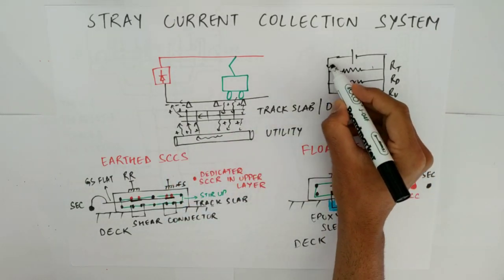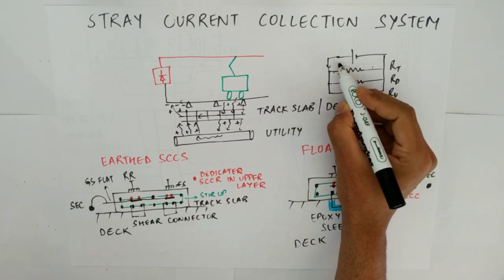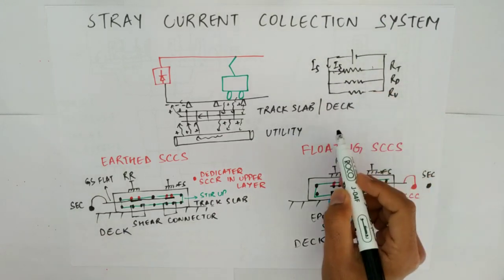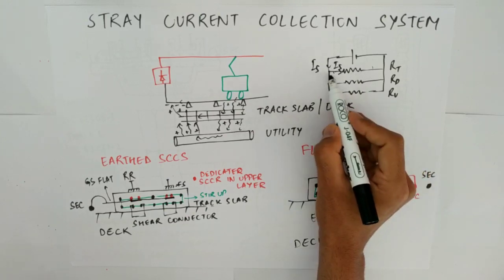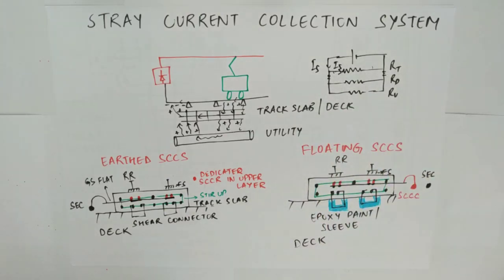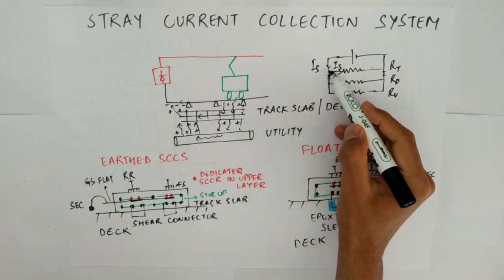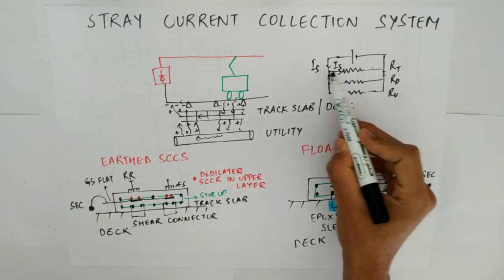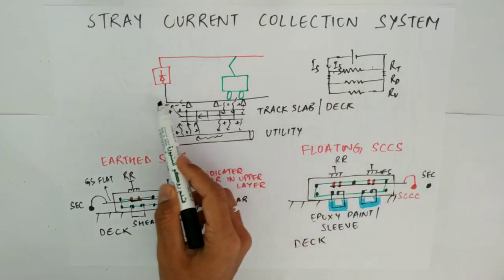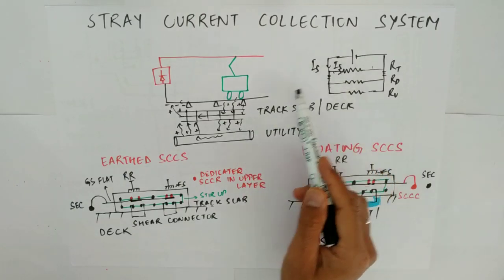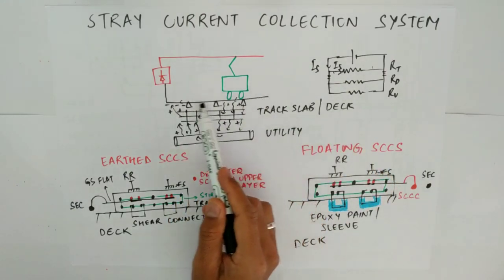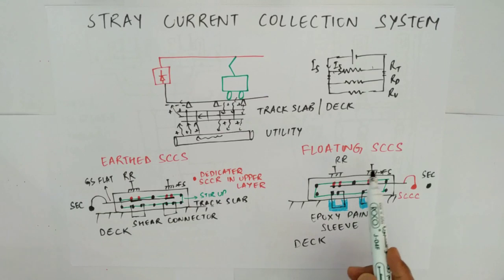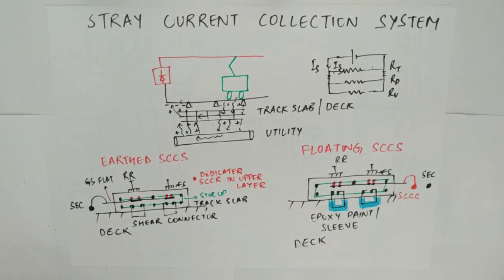By reducing this resistance, the stray current that is flowing will all enter into the track itself. By reducing the resistance RT and increasing the resistance below, the current will not go below and will remain here — which is what we do in case of running rails. In case of running rails, we try to provide design provisions to reduce the longitudinal resistance and increase the insulation. This concept is followed by the floating stray current collection system.